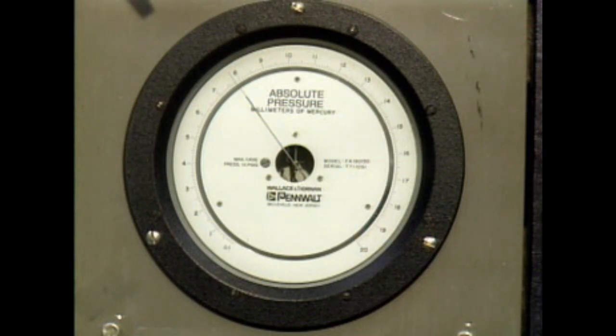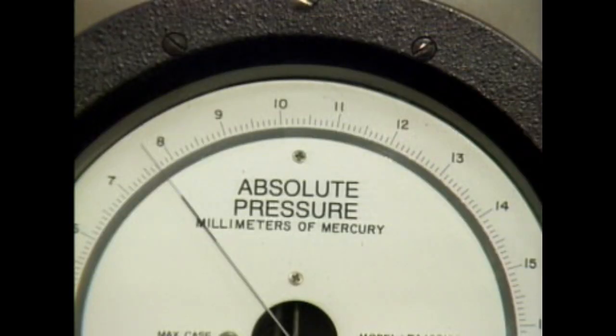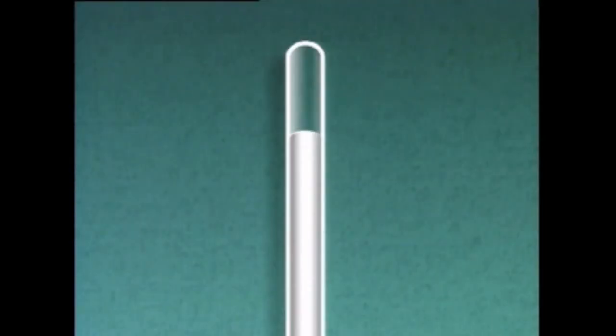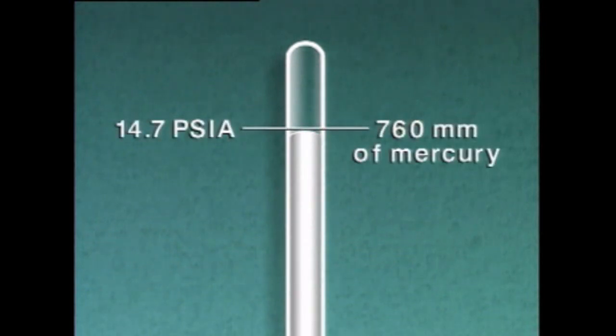Absolute pressure isn't always expressed in PSIA. For example, this instrument indicates absolute pressure in millimeters of mercury. Millimeters of mercury refers to the height of a vertical column of mercury that a given pressure will support. For instance, atmospheric pressure of 14.7 PSIA will support a vertical column of mercury that's about 760 millimeters in height.